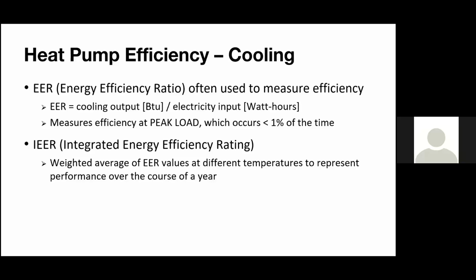So the big takeaway here is EER is perfect for conventional equipment, on-off equipment. It's going to give you an accurate reading on how it operates. EER for a variable speed is not going to tell you the full story, and you might want to look elsewhere, which is IEER, which is going to give you that full story.